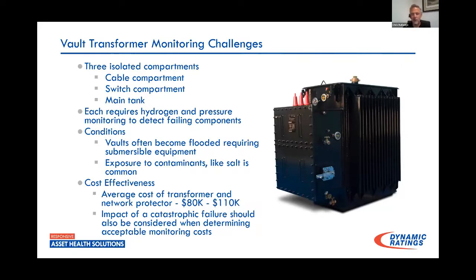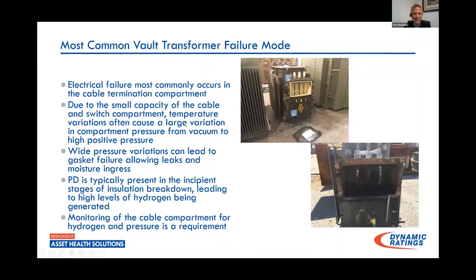And the same for the bank breaker, the protector on the other side of the substation transformer. We're not looking at them at all. We're doing a 5-year maintenance cycle. And again, I've seen several transformers fail simply because a breaker failed to operate. But that would be a talk for another time. So these were some pictures I had of some actual failures, and you can see that these most frequently occur in this cable compartment. That was where I was seeing most of my failures happening. And when I say most, I'm thinking 85, 90% of the time, this was what I saw after a failure.